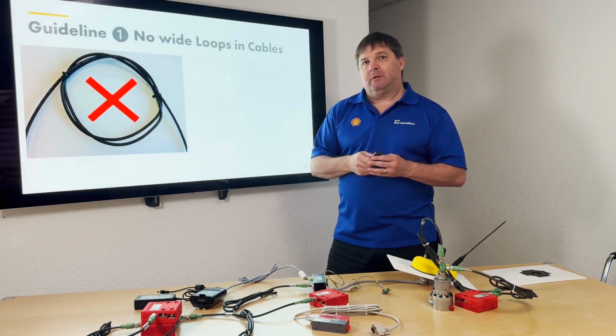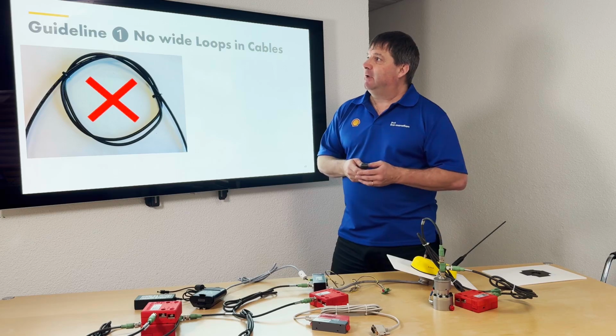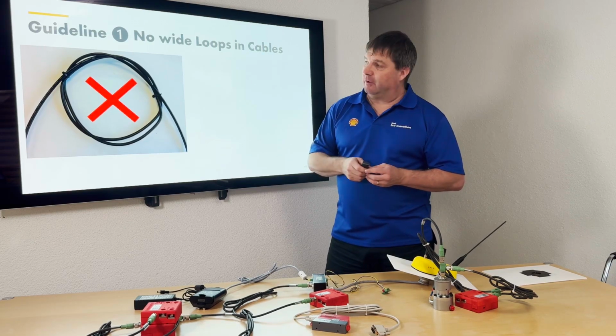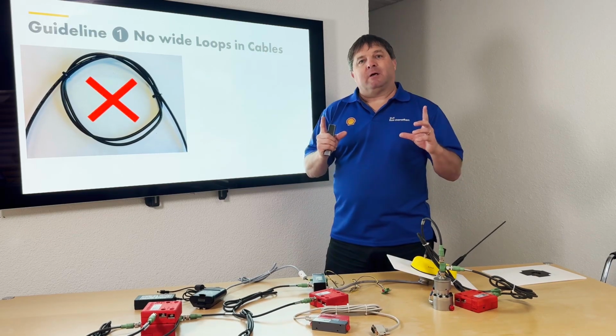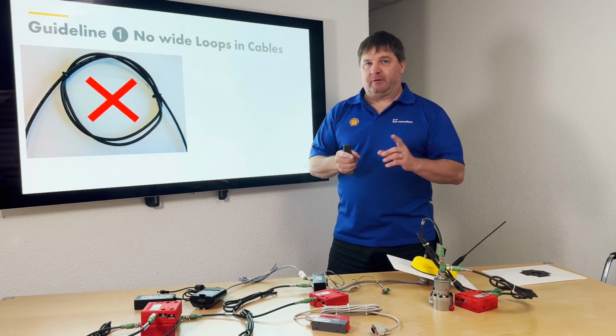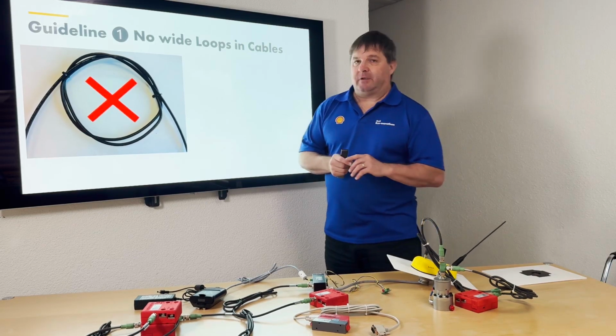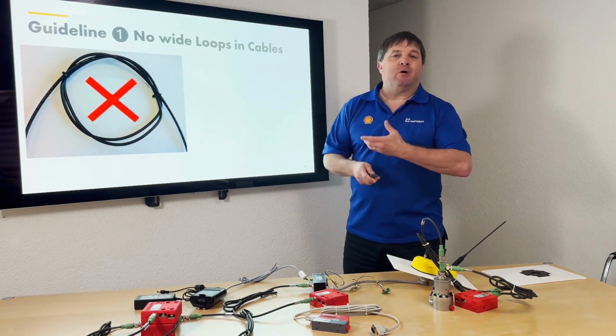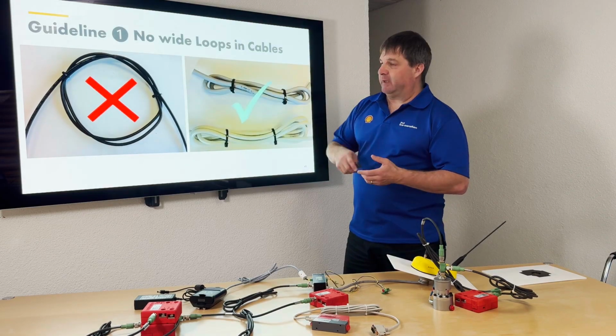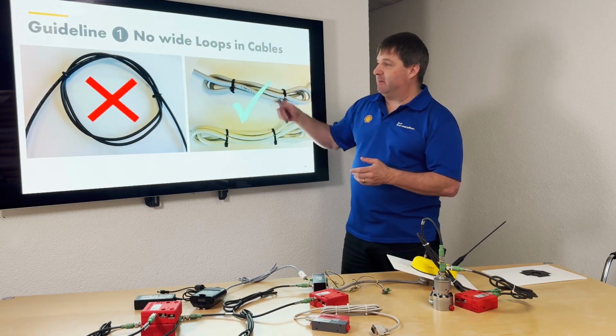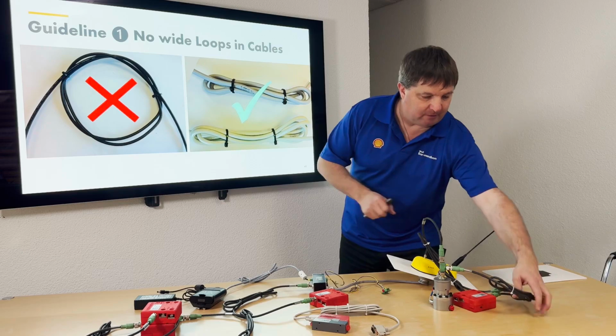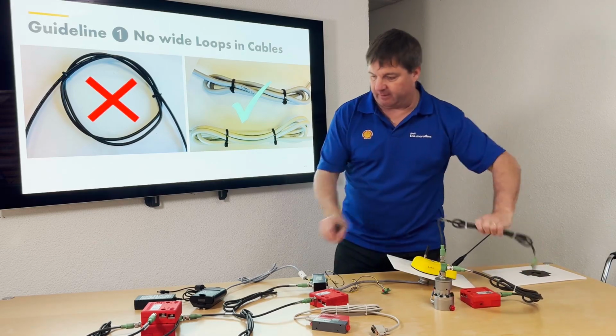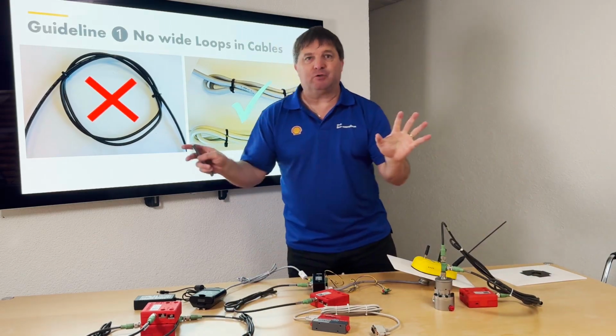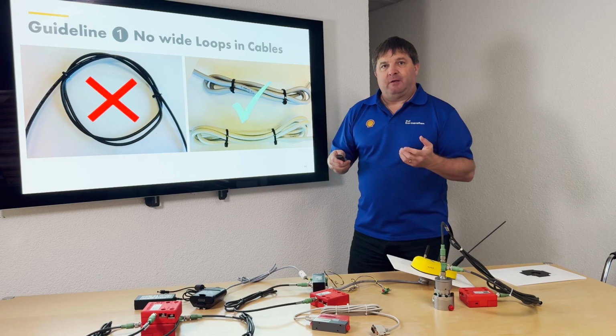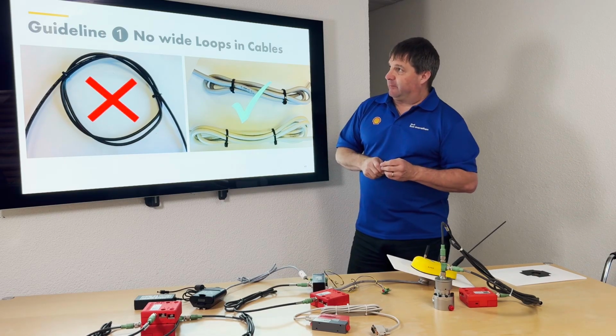Some guidelines now: don't use loops. A loop will always pick up noise from the environment, acting like an antenna, so we must ensure there is no area. What we can do is wind the cables up and make them flat, like you see here, flat cable, flat cable, flat cable, so there is no chance electrical noise is picked up by the telemetry system.